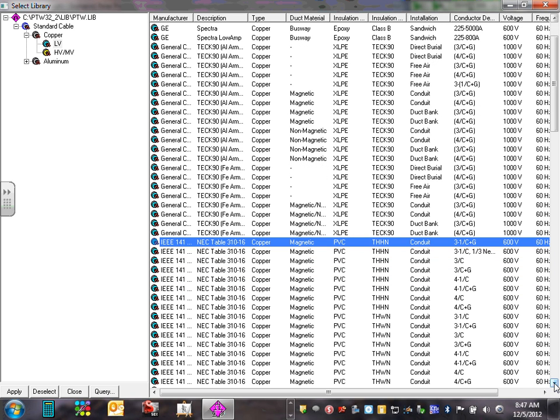Now, I want to remind you, Jeff, can you tell me, please, how many runs did you guys do for your system? And what's the size? For this is coming from the service. What was it? 250. Okay, so when we size them, guys, we use 2 runs of 250s, THHW, it's wet, in a PVC conduit. Remember, it's PVC, it's a wet conductor, so I need to pick a conductor that's wet and in a PVC.